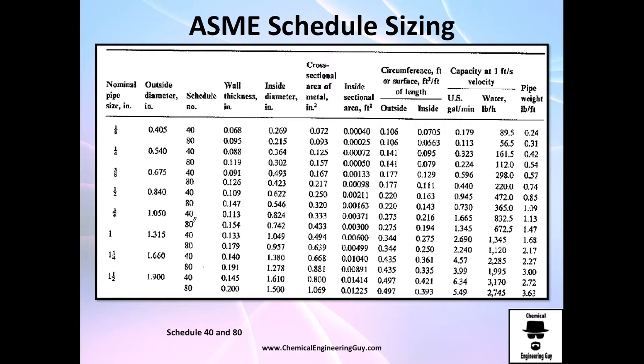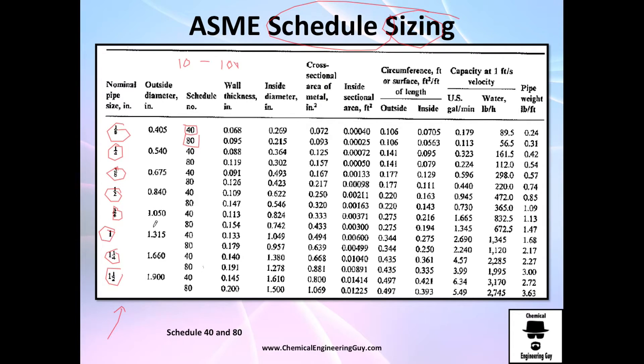To find the actual dimensions, we need ASME tables that show schedule sizing. This table shows only schedule 40 and 80, but you can find others with schedule 10, schedule 100, and more. The table lists sizes from one-eighth inch up to one-and-a-half inch, showing the outside diameter — which, as you can see, has nothing to do with the nominal size. For example, a one-inch pipe is actually 1.3 inches outside.